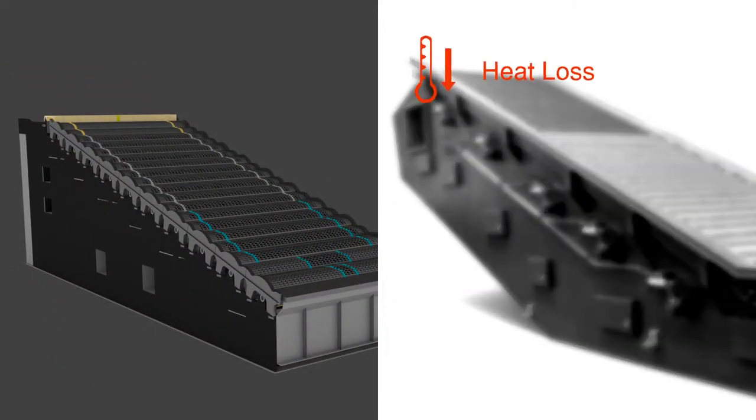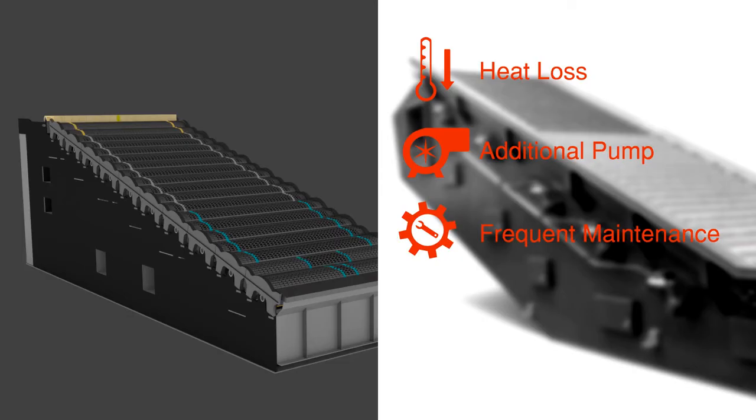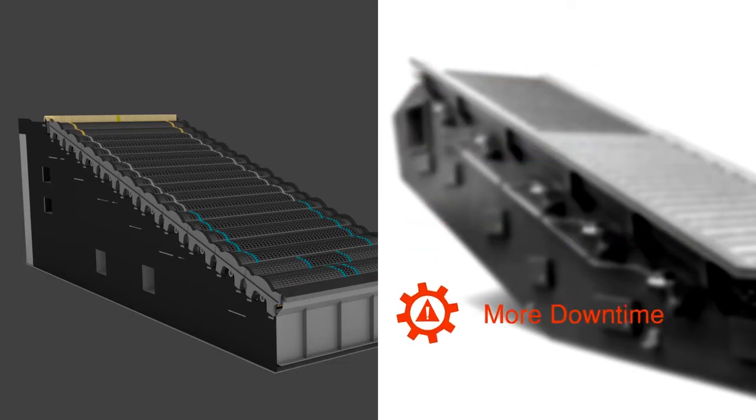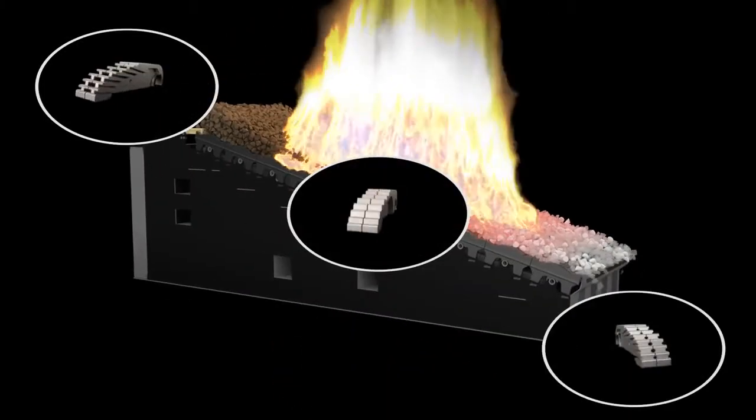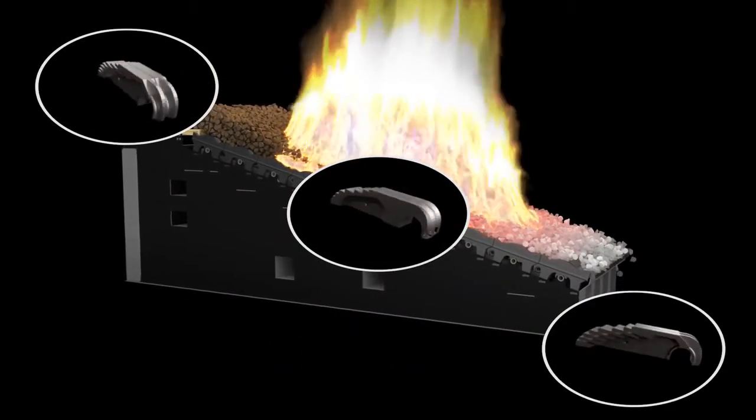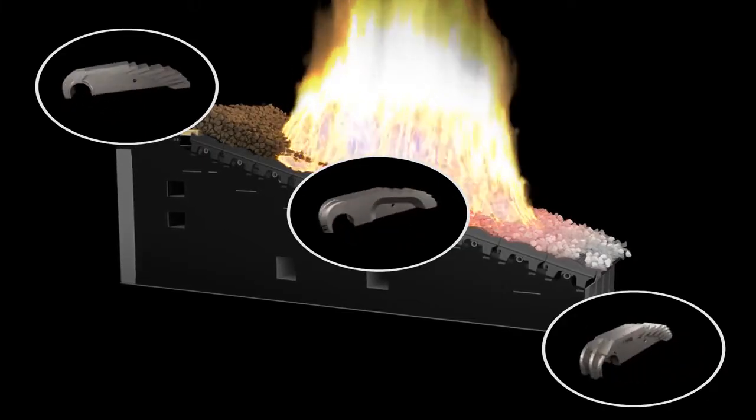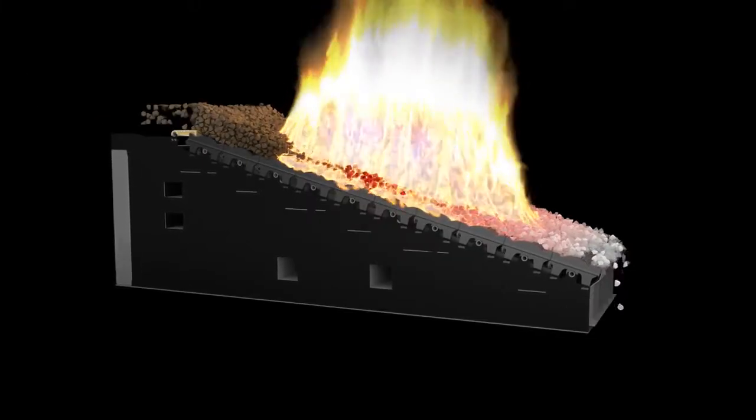Water cooling causes heat loss and requires an additional pump for water circulation and is prone to frequent maintenance. Downtime is more in the case of failure of water cooling system. Castings are available in three different metallurgical compositions depending on temperature zones, ensuring longer life of casting.